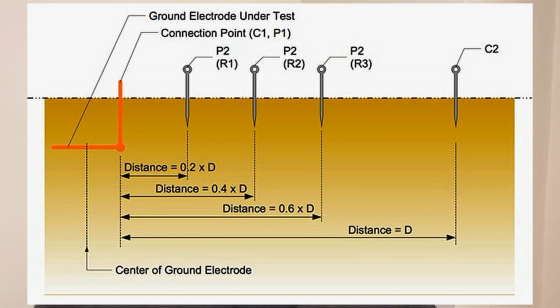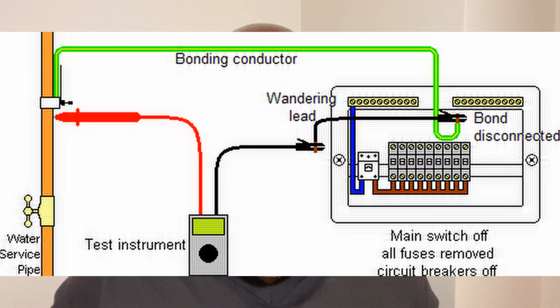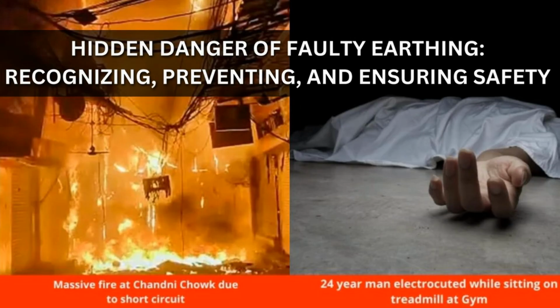Earthing is not about connecting a wire to a ground only. It's about measured resistance and fault clearance time. In many new homes, sometimes the earth rods are too short. Sometimes the earth rods are too close together, and that impacts the resistance. Sometimes the soil resistivity is ignored. The earth continuity sometimes is never tested. We have earth continuity tests, insulation resistance tests, and earth resistance tests. These tests all need to be done and the values ensured to be compliant before your building can be deemed to be safe. A poor earth means faults do not clear fast enough, allowing cables and enclosures to overheat. And if you have overheating risk, you know what that leads to, potentially a fire.